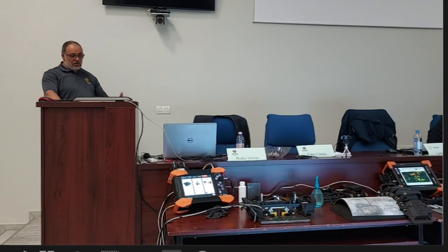Here's an example of a reformer tube, made of carbon steel. It's a difficult or challenging application because of the material itself. The material is ferromagnetic, so permeability is not always constant along the tube. We have to implement some strong magnets in the probe to saturate the material locally and still be able to detect the defect.